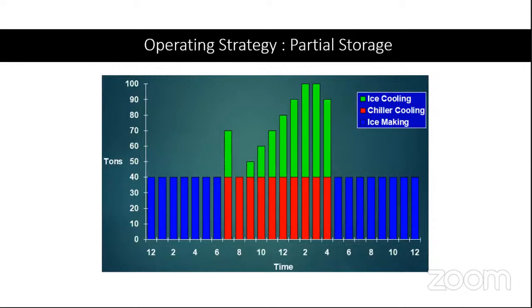Now there is partial storage operation strategy. This is also possible. Partly the load, these red bars, is being taken care of by the chiller, and this extra load up here is being taken care of by thermal storage, and the chillers were busy charging the thermal storage tank at night time. These are the night hours.